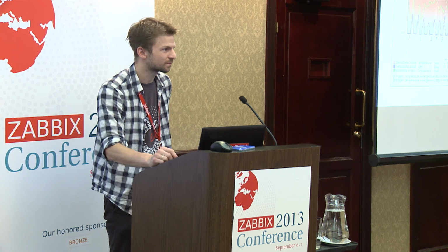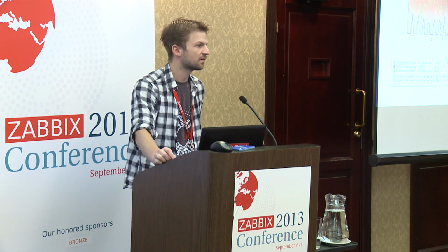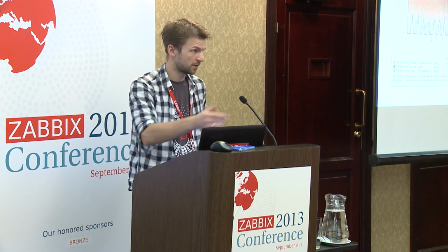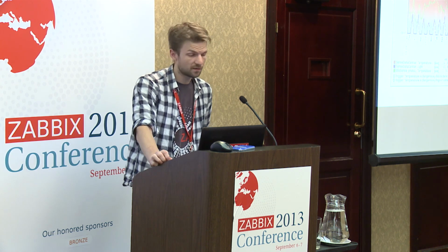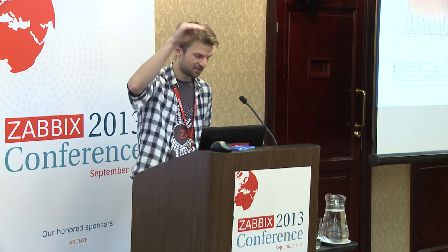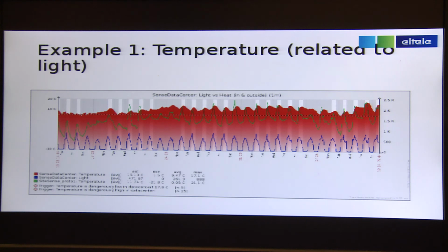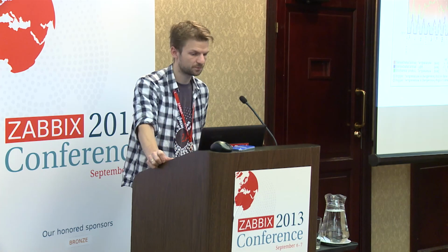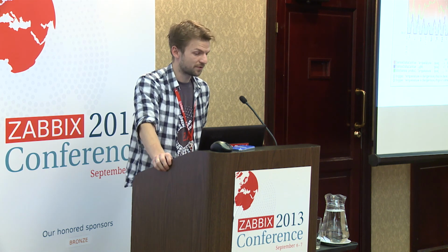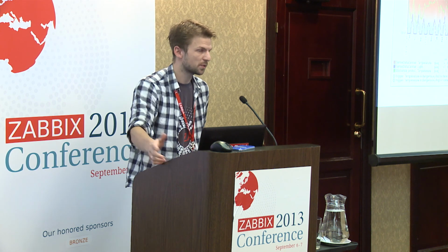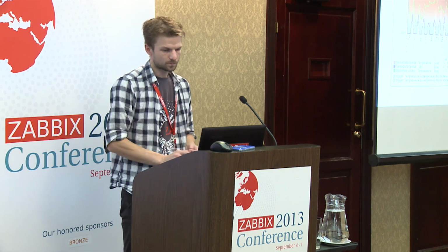So what does that mean? Daylight, of course. And you're right, we're measuring on the inside, so we're talking about windows being involved. The light obviously drives the temperature, mostly outside, but also on the inside. You see the same spikes pushing on each other all the way up. So from this graph alone, I know that this data center should be better isolated and have their windows shaded. Simple measures.